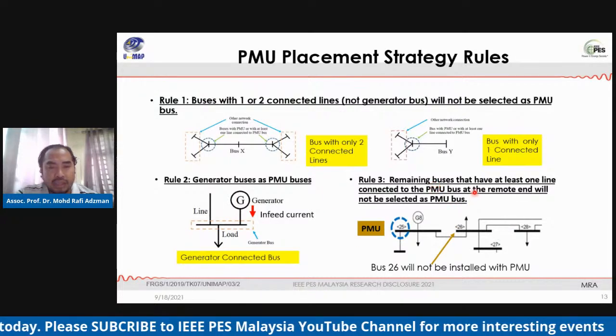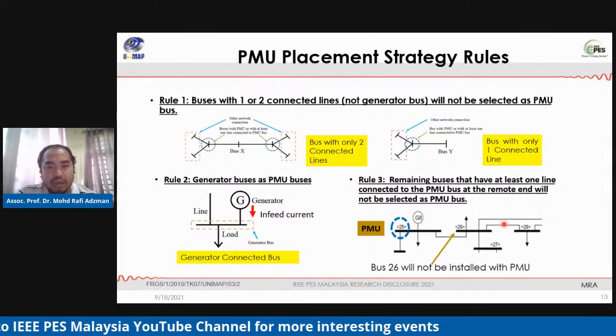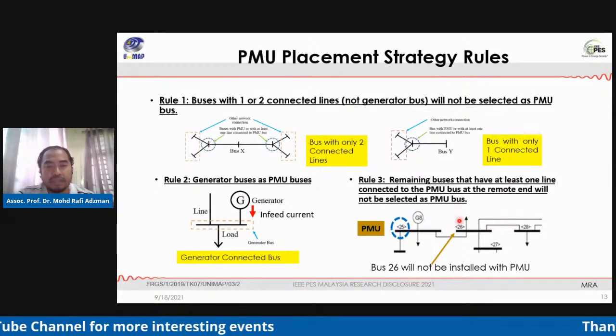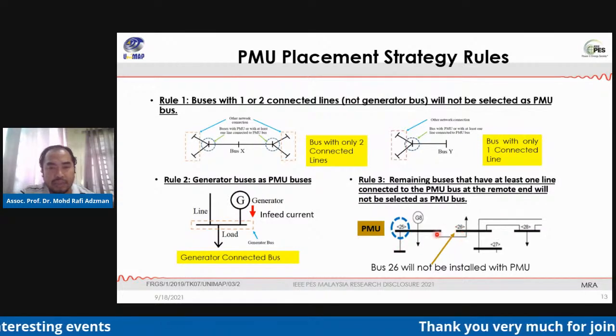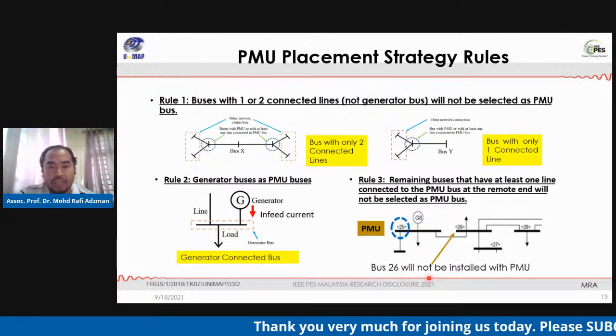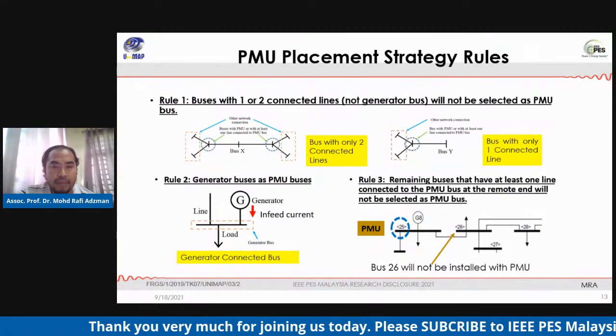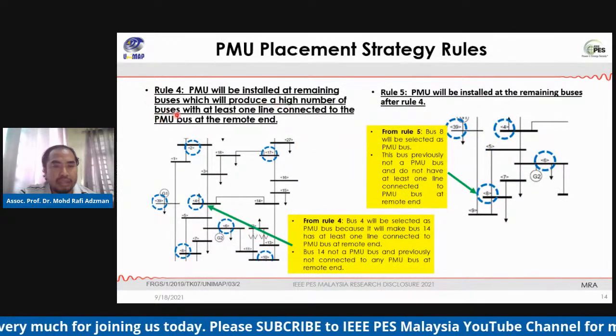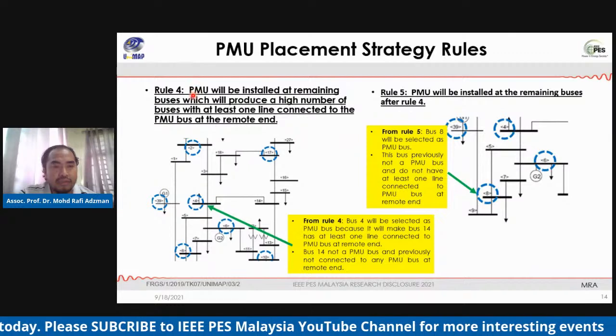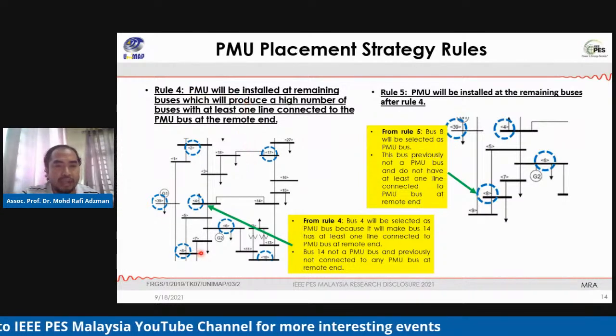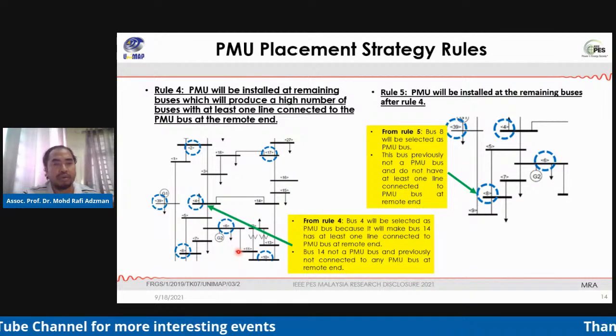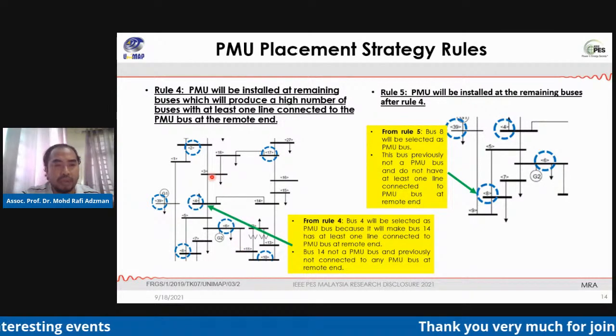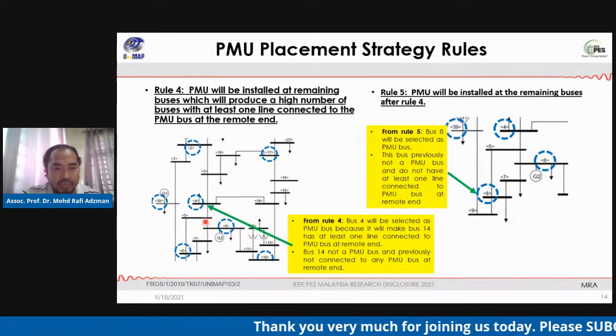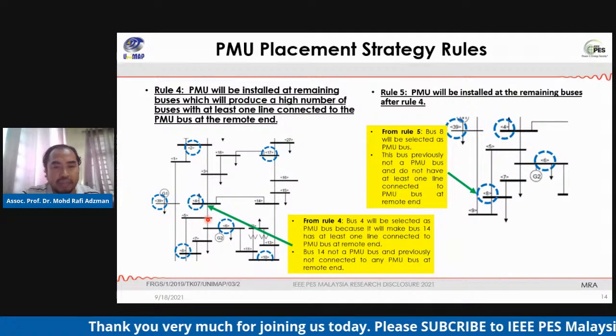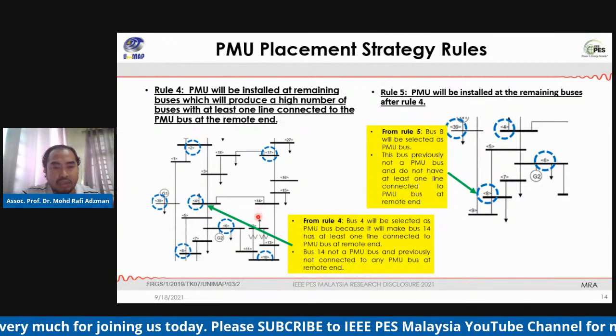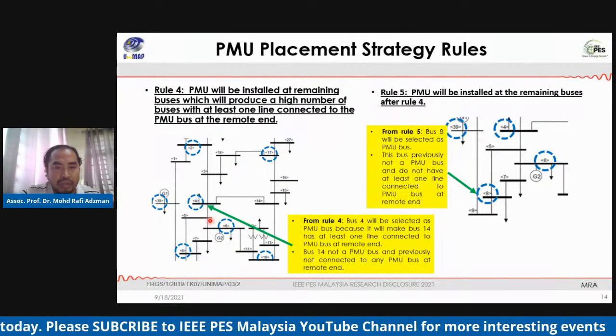Next, in rule 3, the remaining buses that have at least one line connected to a PMU bus at the remote end will not be selected as a PMU bus. For example, here, bus number 26 will not be installed with a PMU. And next, we have rule number 4. For this rule, a PMU will be installed at the remaining buses which will produce a high number of buses with at least one line connected to a PMU. For example, here, bus number 4 will be selected as a PMU bus because it will make bus 14 here have at least one line connected to a PMU bus at a remote end.